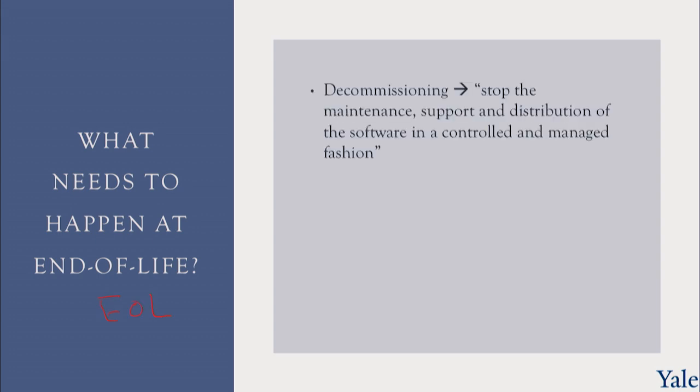That means end of life. So this is a process that's called decommissioning, and as some of the regulatory documents, in IMDRF speak here, we are stopping the maintenance, support, and distribution of the software in a controlled and managed fashion. Let me underline controlled and managed. We don't just call people and say, tomorrow the software is retiring, we're no longer supporting it.